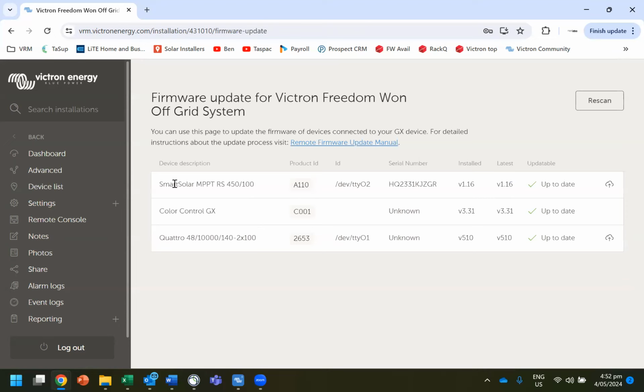So we can see these three devices are connected currently and online, and these are ones that we have access to update the firmware. And we can see there that the firmware is all up to date. So that's great. If it's not, you can go through and click update the firmware. Be aware that when you update the firmware on the Quattro inverter or any inverter, it is going to power cycle the inverter down and then back up again.